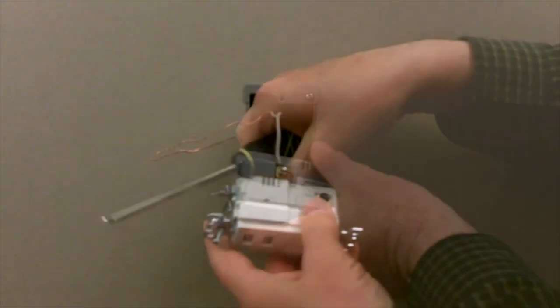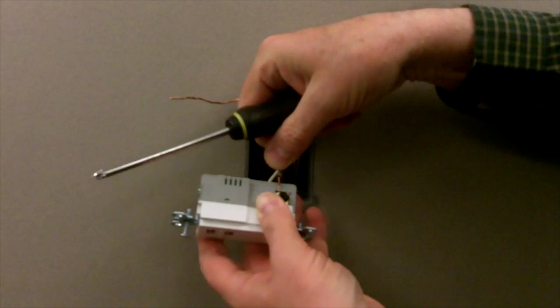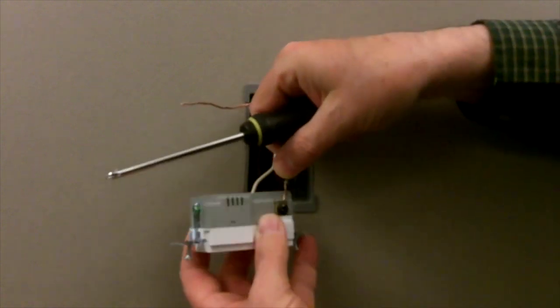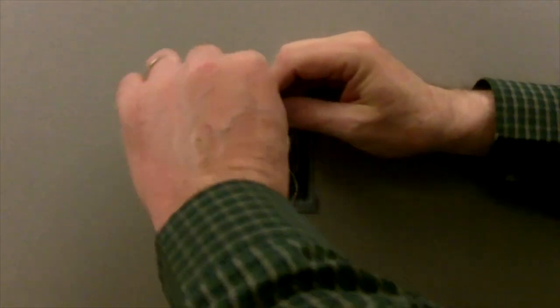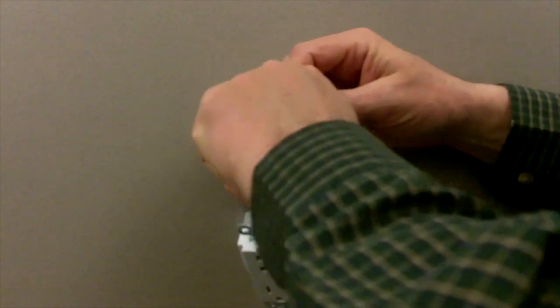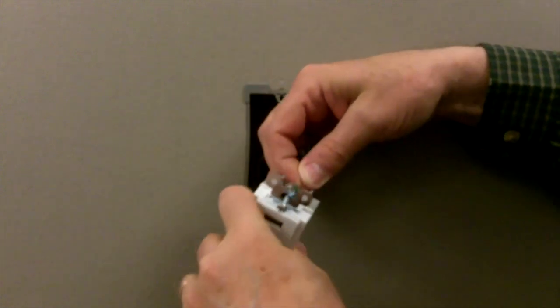Connect the wires to the device. Neutral to the silver terminal screw, hot to the brass terminal screw, and your ground wire to the green ground terminal screw. The terminal screws should be torqued to 12 to 14 inch-pounds.